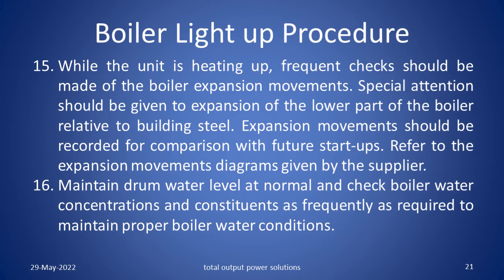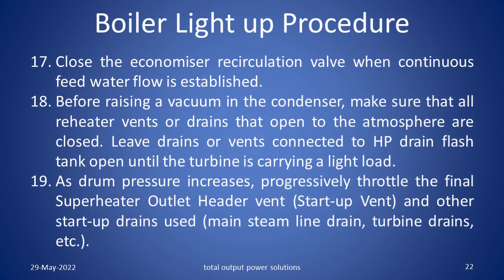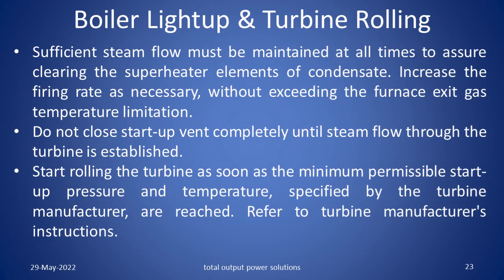Refer to the expansion movements diagram given by the supplier. Maintain the drum water level at normal and check boiler water concentrations and constituents as frequently as required to maintain proper boiler water conditions. Close the economizer recirculation valve when continuous feed water flow is established. Before raising a vacuum in the condenser, make sure that all the reheater vents or drains that open to the atmosphere are closed. Leave drains and vents connected to the HP drain flash tank open until the turbine is carrying a light load. As drum pressure increases, progressively throttle the final superheater outlet header vent, i.e. start up vent and other start up drains used, i.e. main steam line drains, turbine drains, etc. Sufficient steam flow must be maintained at all times to assure clearing the superheater elements of condensate.